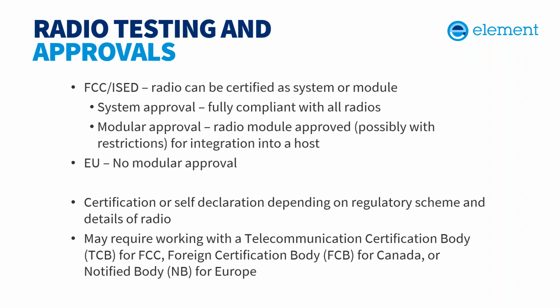Radios can also be certified as modules, and when they are, they're tested by the module manufacturer to meet the radio requirements. So basically, the module receives modular approval. The complexities we won't get into today, but the point of modular approval is that if a product manufacturer, in this case medical device manufacturers, integrates an approved radio, and you follow the grant conditions from the FCC and the integration instructions from the module manufacturer, no additional certification work will be required and only a minimal amount of testing, if you follow those two items, the grant conditions and integration instructions.